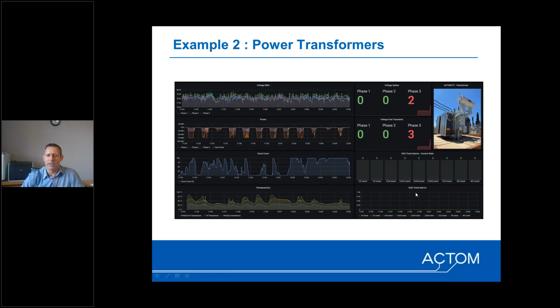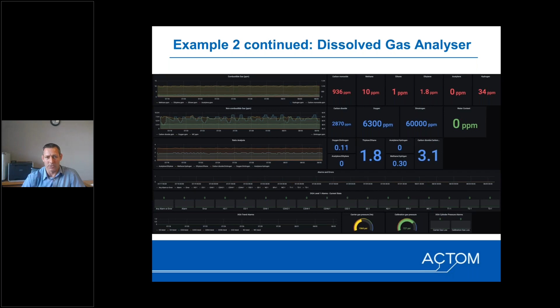On power transformers, things you will typically look at are voltage, power, and temperature is quite important, and specifically the gases, which Wilma also touched on. There's online gas monitoring which monitors about 9 gases, and these will indicate whether your transformer needs some repair services.